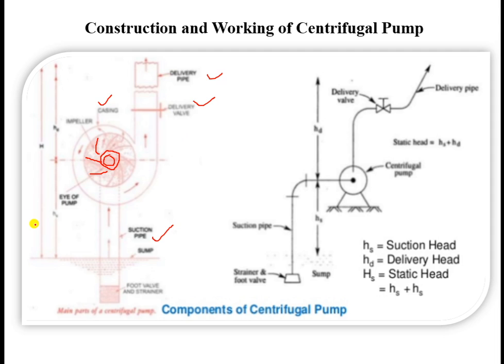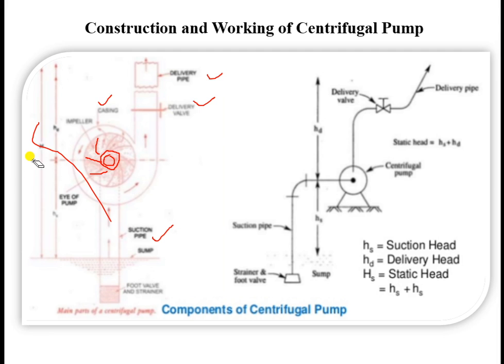The total head is used to classify pumps as low head, medium head, and high head pumps. The total head is the addition of the discharge head and suction head — that is, the depth from which water is lifted plus the height at which water is supplied to the destination.